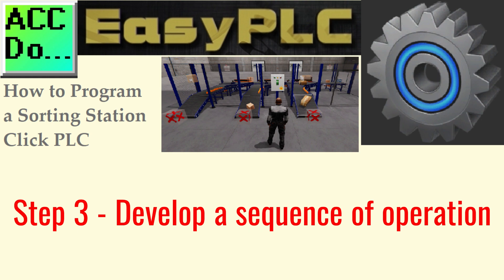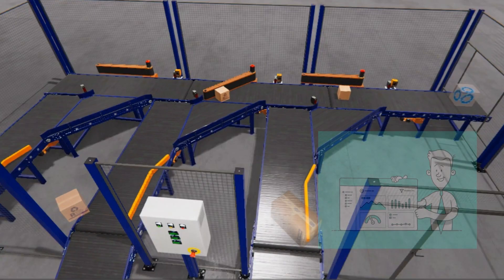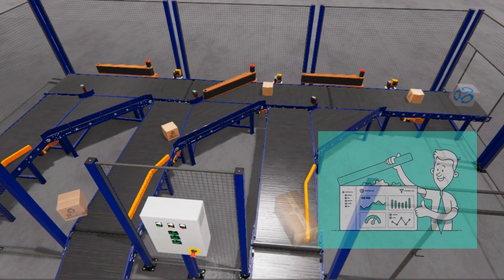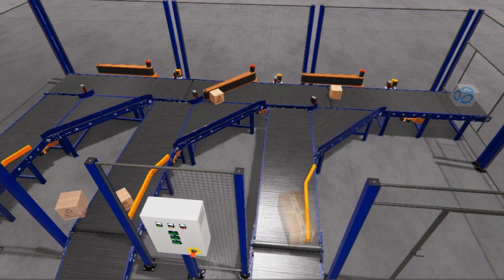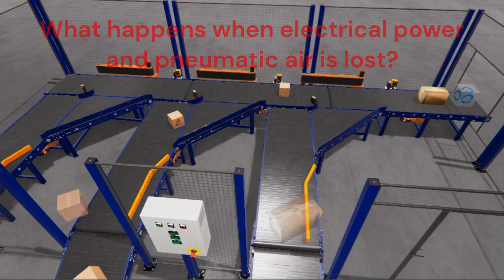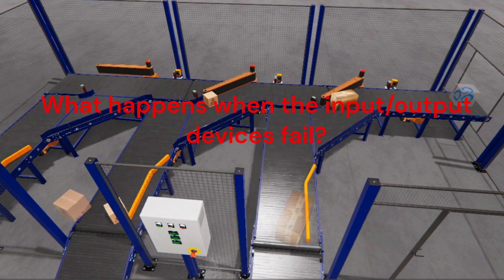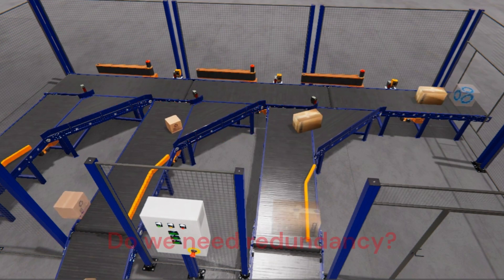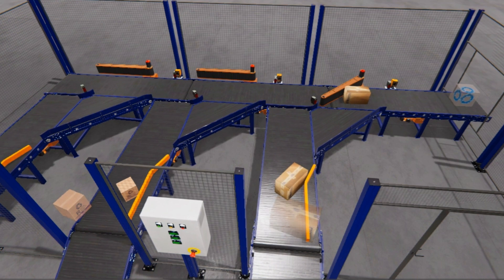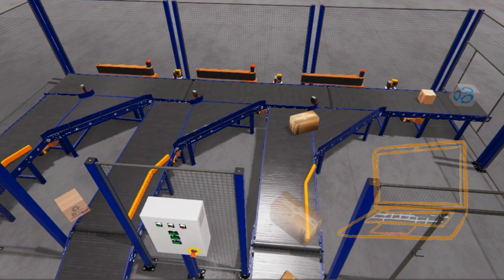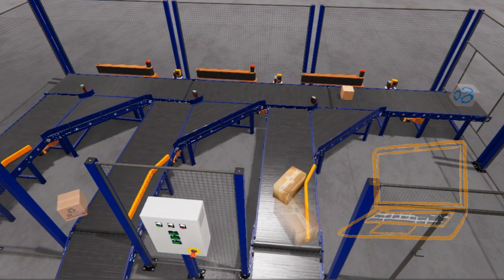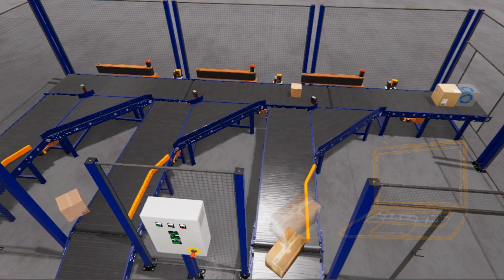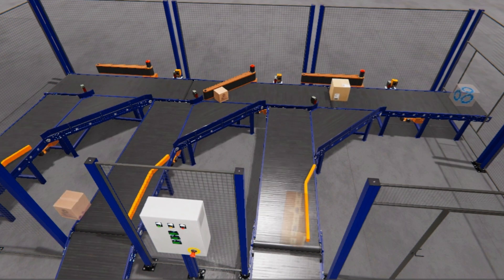Step 3. Develop a logical sequence of operation. A flow chart or sequence table is used to understand the process that needs to be controlled thoroughly. You must also answer questions like the following. What happens when electrical power or pneumatic air is lost? What happens when inputs and outputs fail? Do we need redundancy? This step is where you can save yourself a lot of work by understanding everything about the operation. It will help you from continuously rewriting the PLC program logic. Knowing all these answers up front is vital in the development of the PLC program.